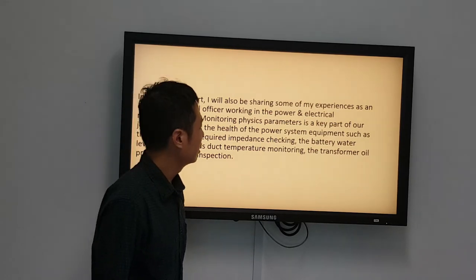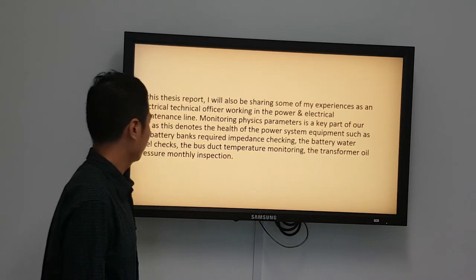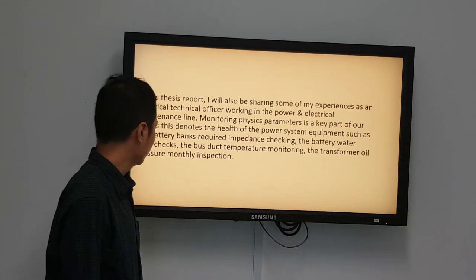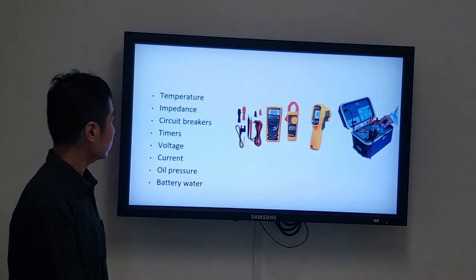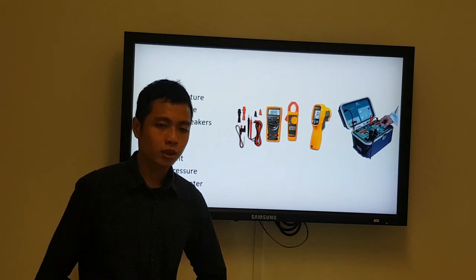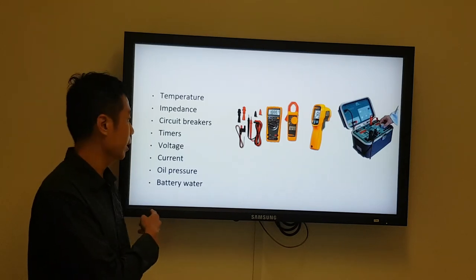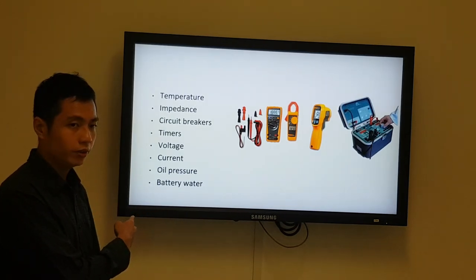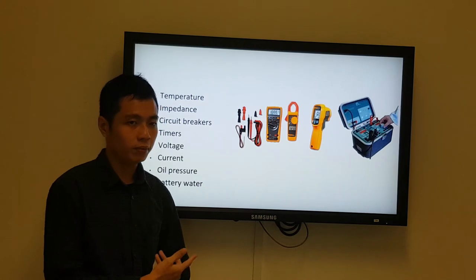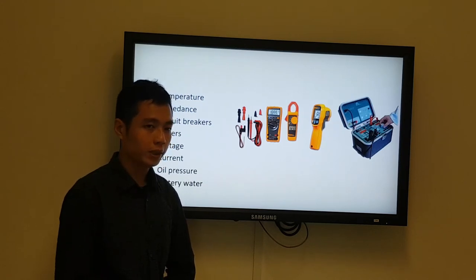Monitoring physical parameters is a key part of the job, as it shows the health of power system equipment such as battery banks, impedance checking, battery water levels, bus bar temperature monitoring, and transformer pressure monthly inspections. These physical parameters are key to intelligent energy management — they include temperature, impedance, circuit breakers, timers, voltage, current, oil pressure, and battery water levels. These parameters are critical when the maintenance team conducts monthly inspections to maintain the power system.